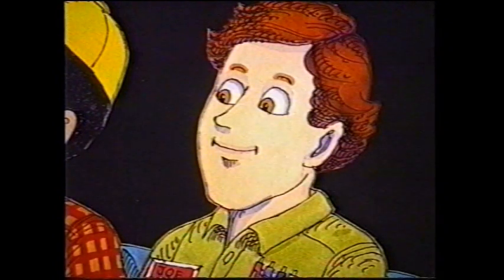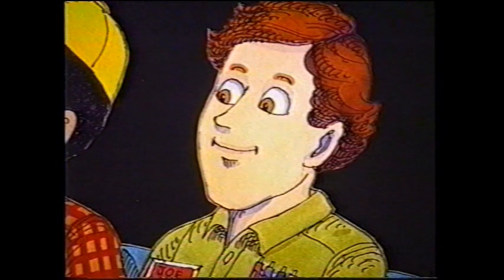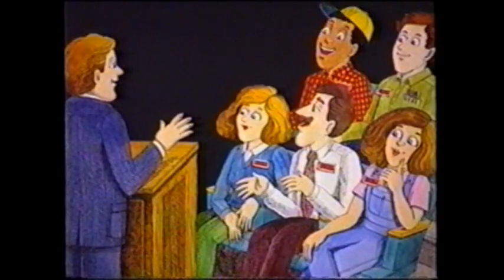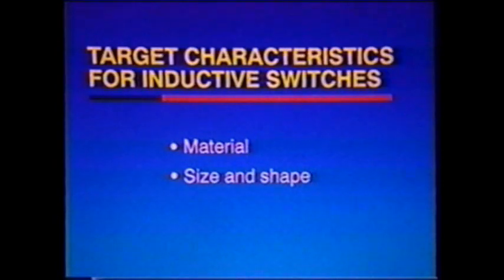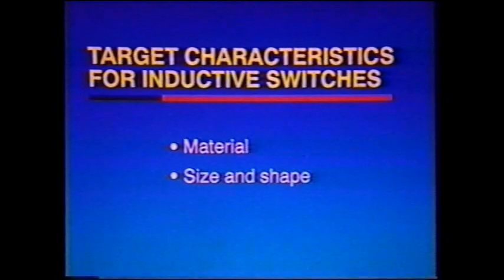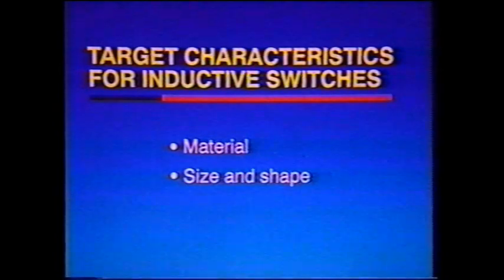Why not operate the switch at 100% of its range? One example of why you want to operate in the 50% to 80% range is to allow for wear of the actuating device. The testing for nominal range uses a mild steel target that is a specified size. The actual material, size, and shape will determine the sensing range in a real-world application.